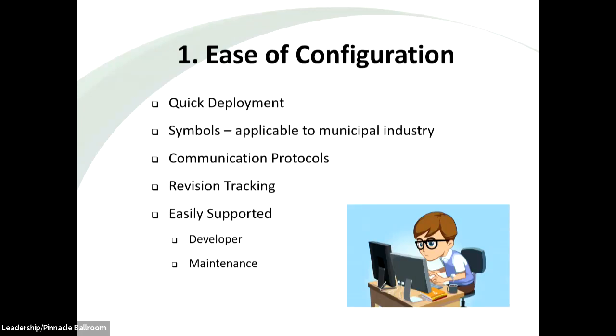So the first one, ease of configuration. What we're looking for in future SCADA systems is something that can be deployed relatively quickly, which keeps the cost down of configuration and building the graphics. To build the graphics, to put a pump object on a screen, you want that pump object to be what we call a symbol, a template, an object that you can just drag, drop it on a screen, and then animate it. When you animate it, it represents the running or stopped status. So if you have these symbols available, your configuration time will certainly be a lot less compared to having to build these symbols from scratch.